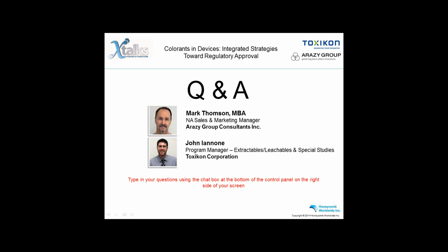Our next question here. What are some of the recommendations for testing metal devices for short-term skin contact? So in terms of biocompatibility for a metal device with short-term skin contact, if there is a conformance and you can confirm that conformance to a specific standard, like different ASTM standards for stainless steels, if you have the ability to conform to that standard and confirm it, then the biocompatibility of that device is defined by the conformance to the standard in and of itself. And that happens quite often with some types of metal devices.